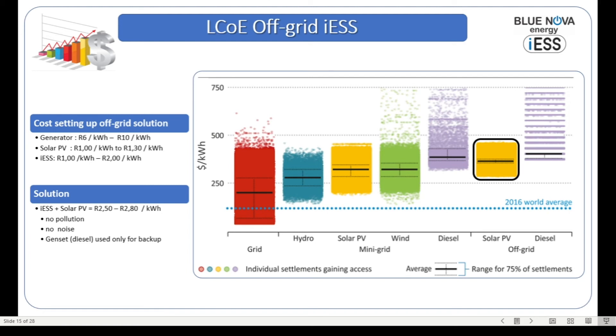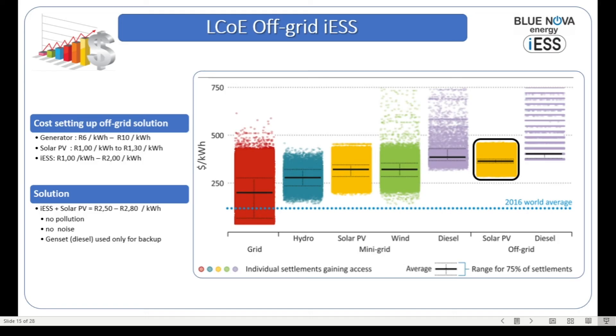If we add an iESS system to a solar PV system, we're looking at a cost of producing electricity in the region of two rand fifty to two rand eighty per kilowatt-hour, which is fixed for more than 13 years. There is no escalation in cost — there is obviously a capital acquisition required, but that would be the average cost to produce a kilowatt-hour at two rand fifty to two rand eighty, compared to a diesel generator running between six and ten rand per kilowatt-hour. The main benefits of a solar PV plus iESS combination are that while it's running there's no pollution, there's no noise, and the generator will only be started in cases of insufficient solar production, not as a general operating principle.